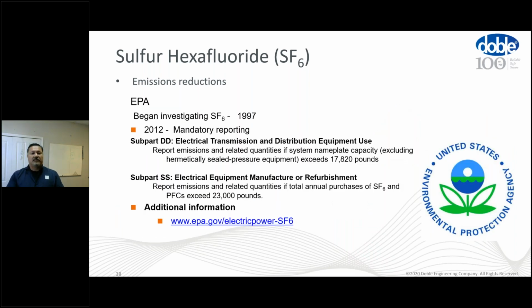And investigating SF6 in 1997, right around that Kyoto Protocol time frame. But the mandatory reporting didn't really kick in until 2012. So a couple subparts to it. So subpart DD, which is for electrical transmission and distribution equipment, basically for utilities that report emissions if their nameplate value exceeds 17,820 pounds. All right.